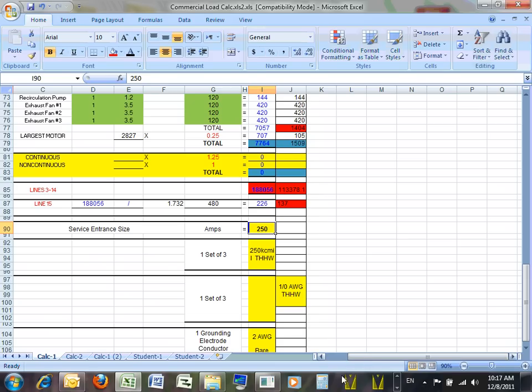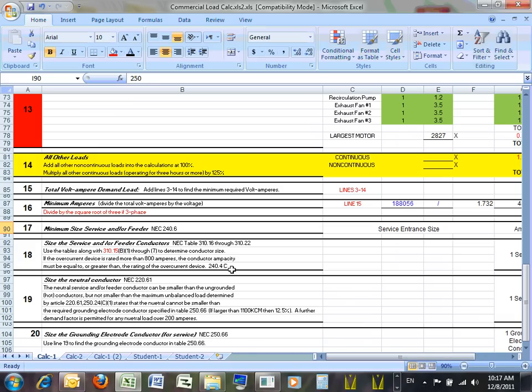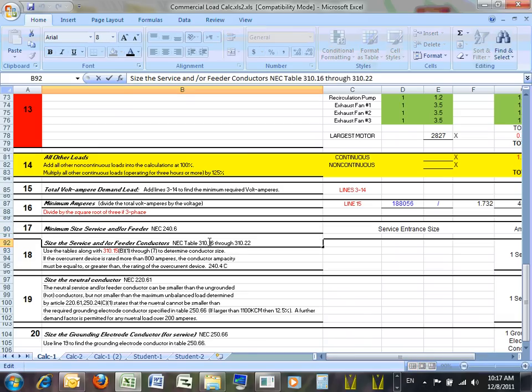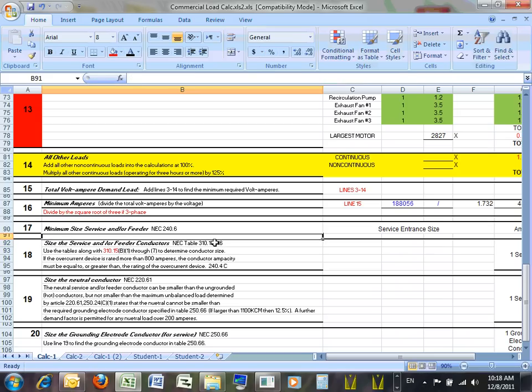The next thing, guys, we're going to size the conductors. This is a quick exercise of sizing conductors. We're going to go to 310, which of course has changed. 310.15(B)(16), now (B)(16). So we're going to go to 310.15 B16. I'm going to delete that one because of the new change in the code. We're going to be sizing these based on 240.4C and all this good stuff.